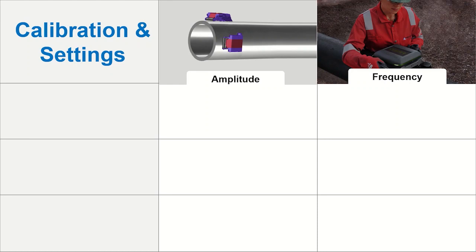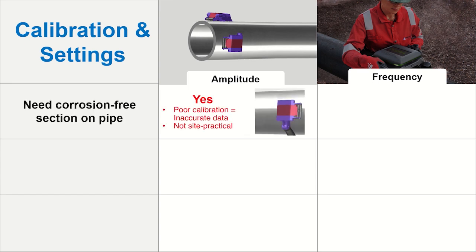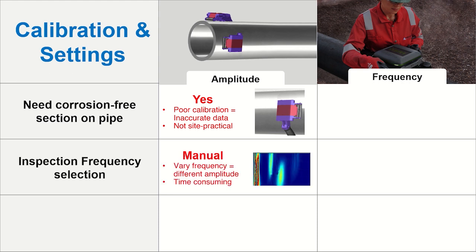When it comes to calibration and inspection settings, amplitude-based measurements such as MRUT require calibration from a corrosion-free section of the pipe. The amplitudes are also sensitive to the inspection frequency selected, which often needs to be manually selected by an experienced MRUT inspector.